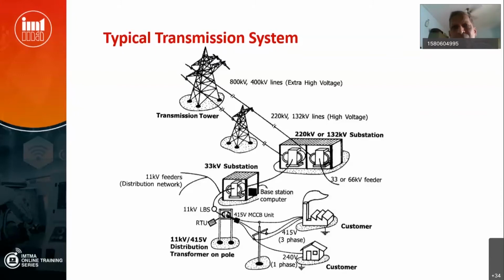There it is again stepped down, maybe 400 kV, and a 400 kV network will be there. It will be distributed in the surrounding area. Again, after 400, it is stepped down to 220 kV, 220 kV to 110 kV. There may be consumers who are getting the supply at 220 kV and 110 kV, large customers. For example, in Bangalore, if you see our wheel and axle plants or large public sector industries, HAL, BEL, they are all getting at high tension voltages. I am referring to cases in Bangalore since I am from Bangalore. Okay, they are getting at higher voltages. So MRPL, for example, in Bangalore, they are getting at the voltage 220 kV. So such large consumers are supplied with high tension, extra high tension voltage. They are tapped at this level. Later on, it is stepped down to 110, 66, 33, depending on the factory or industry size. At different levels, voltage will be tapped. And finally, when it comes to small and mini industries, it will be at 11 kV.